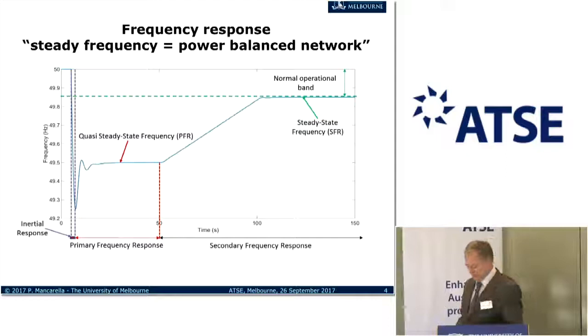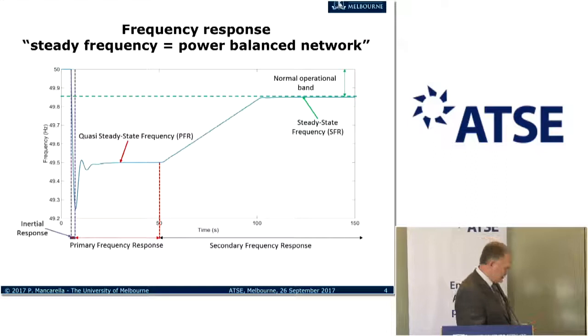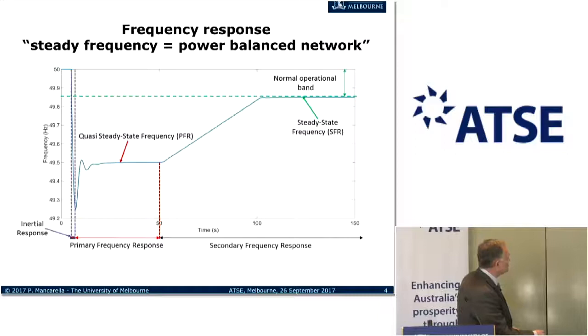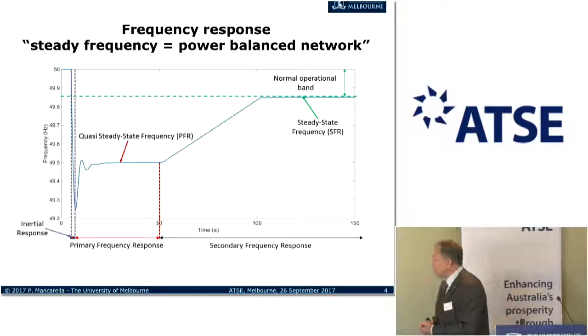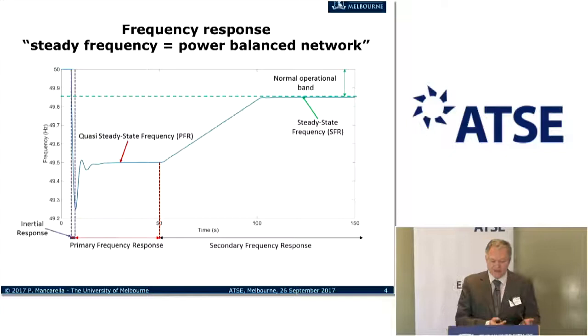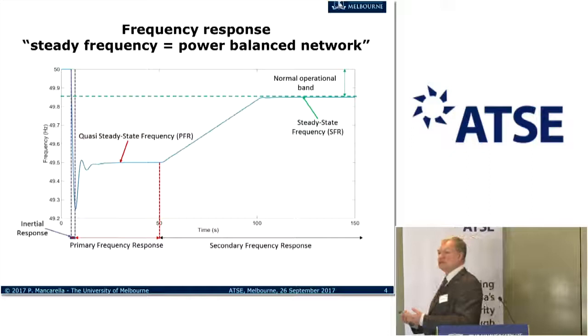Then there is a response dictated by governors that tells you the frequency will respond and go to a minimum somewhere, then restore slightly and come back to a quasi-steady state. That frequency will not be the frequency where we want to be, and then later on, by additional control and command, the frequency will be built up again as more thermal power or other power is delivered to the site to bring that balance back to where we want to be and bring the frequency back.